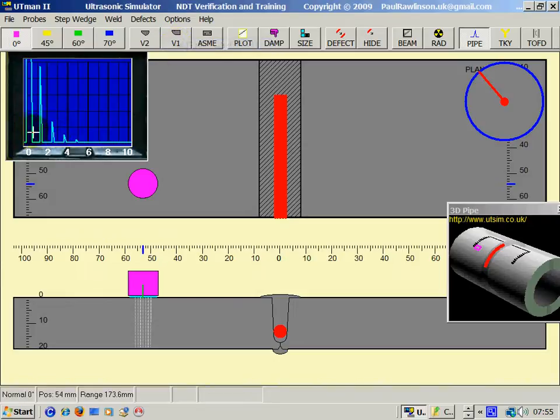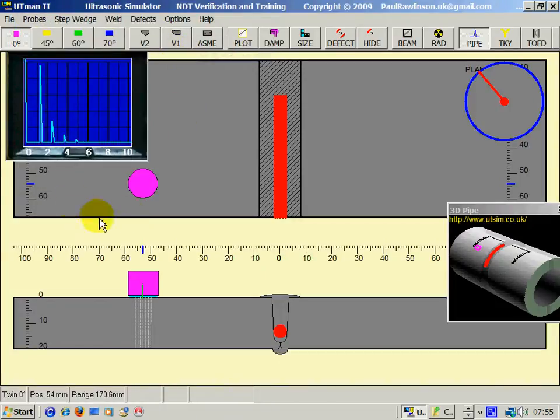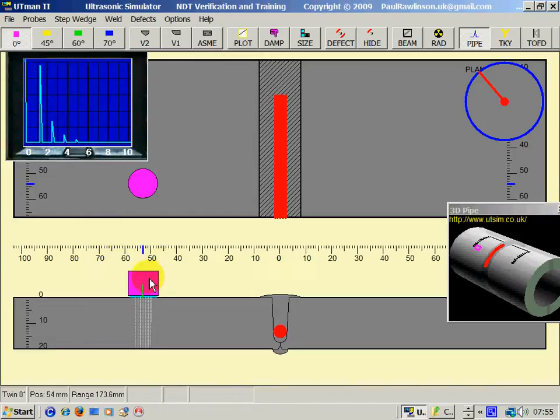Single crystal, this is all initial pulse and dead zone. So with twin crystal, we lose a lot of the dead zone and gain more of the screen to measure thinner sections.